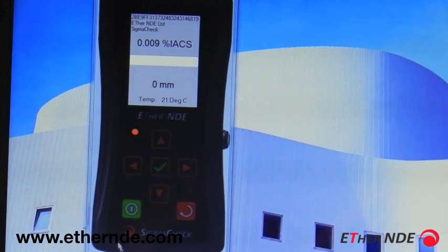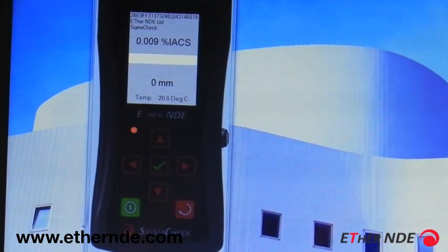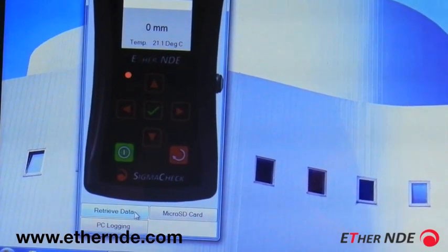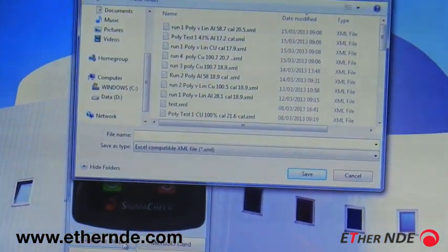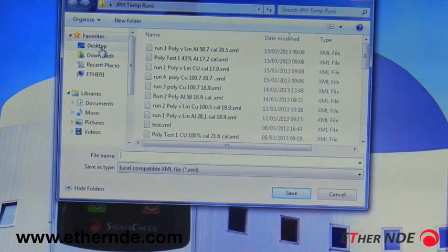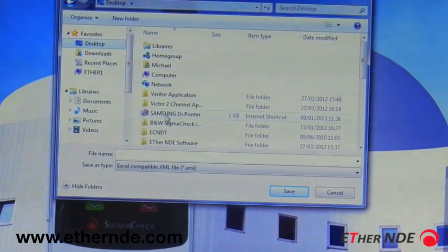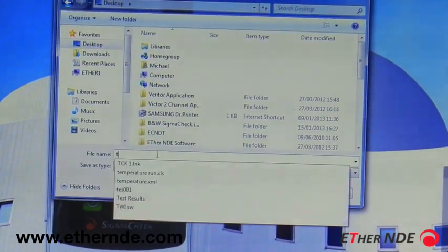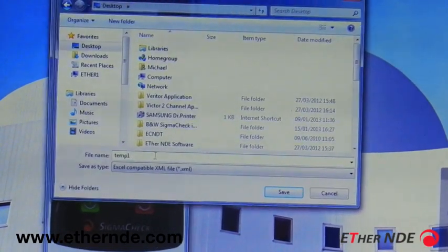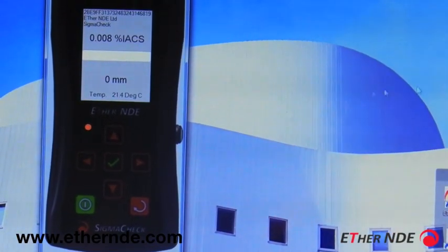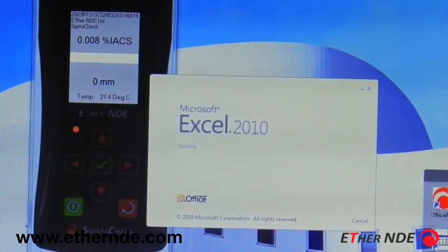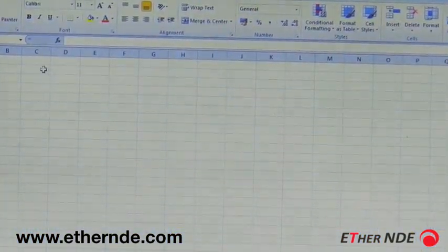At the bottom here we have a retrieve data button, which is specifically for the purpose of retrieving data-logged data. So I click on that — that's uploaded the data. I shall now pick a destination and save it to the desktop, and I'll call it Temp1. Now I can open up Microsoft Excel; any mainstream spreadsheet package is capable of viewing the data.